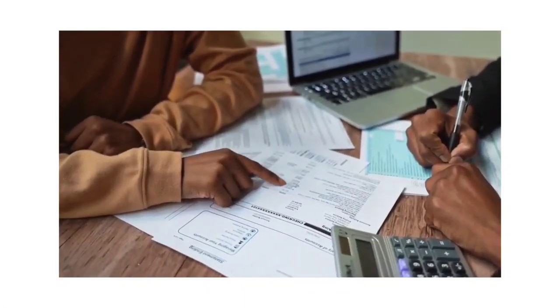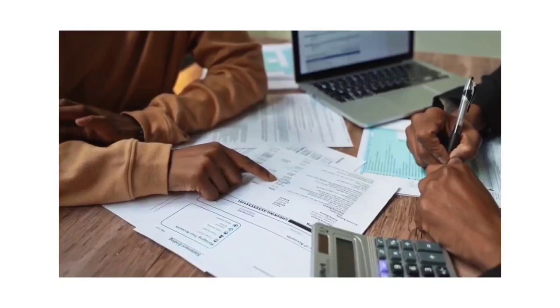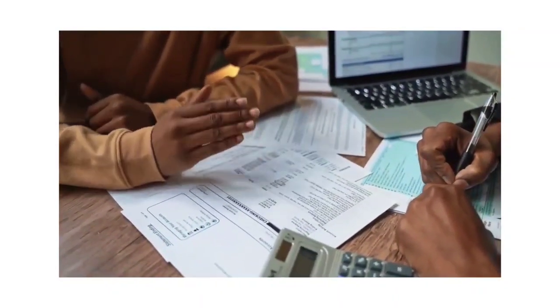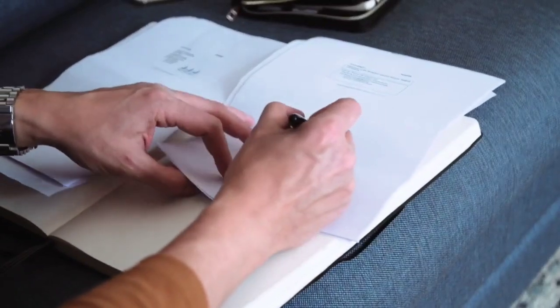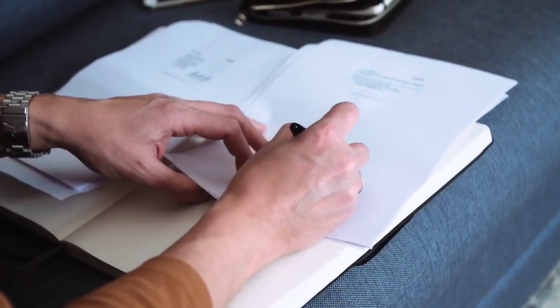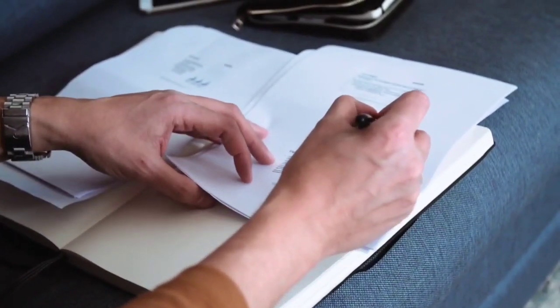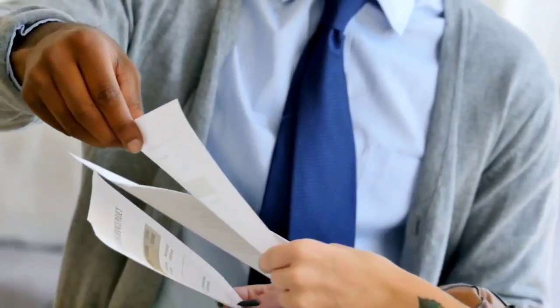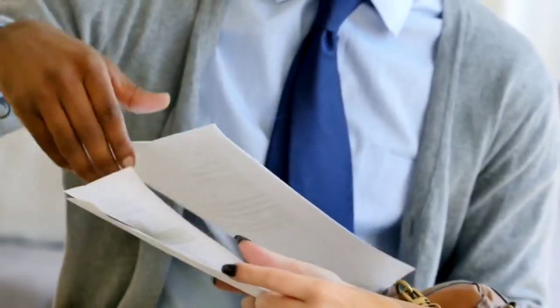Okay, we move now to documentation of all condemnation. If equipment is not repaired or out of use, the device which cannot be used or repaired should be labeled as condemned devices. Such category devices need to be listed and documented.